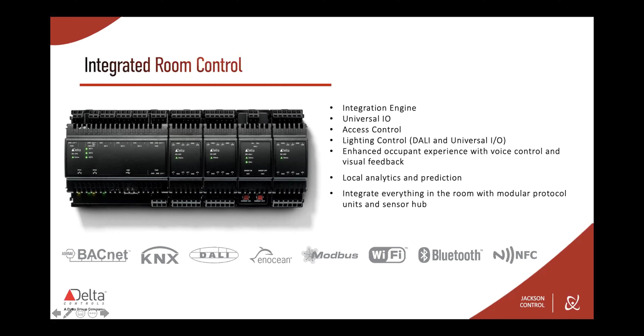It also comes with, you can add IO modules as well. We have what we call an 8 uniput module, so it's 8 points, and through software, no jumpers or anything, those can be software selectable as an input or an output - 0 to 10 volt outputs, 0 to 5 or 0 to 10 volt inputs, 10K thermistor, 4 to 20 milliamp, or digital signals. We also have one with 4 universal inputs and 4 FET or TRIAC outputs.